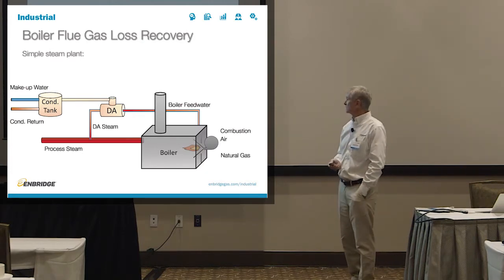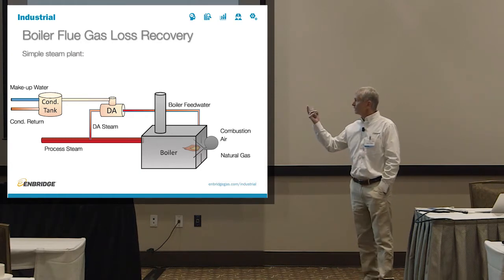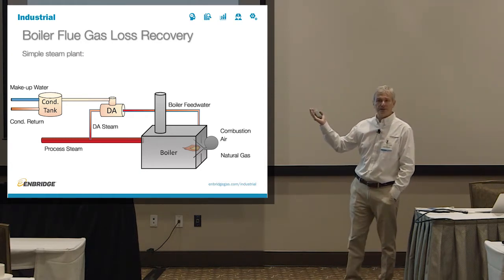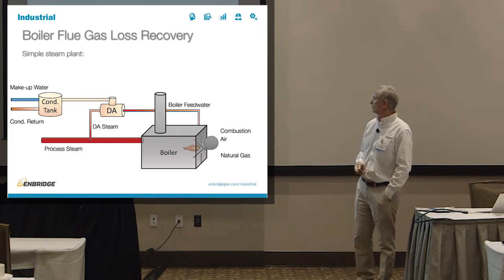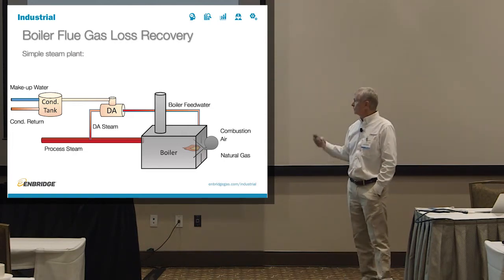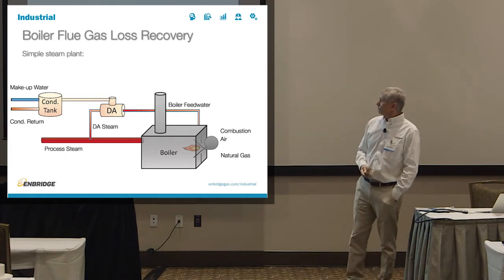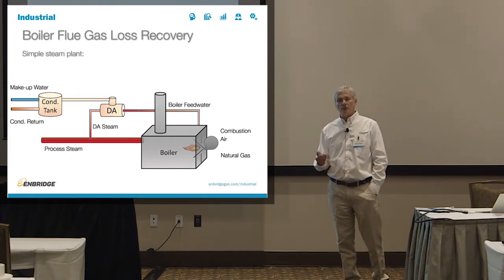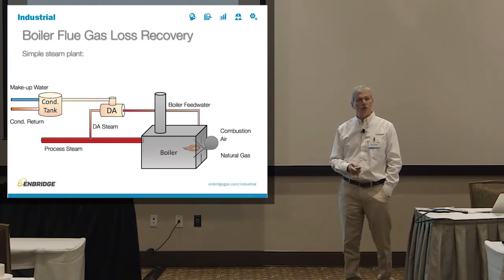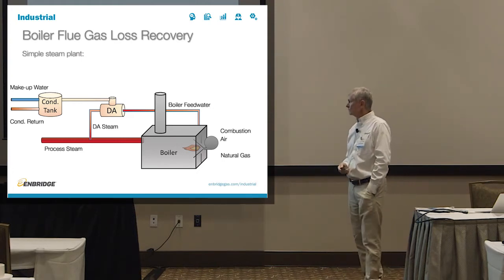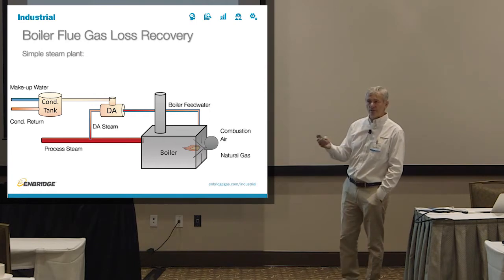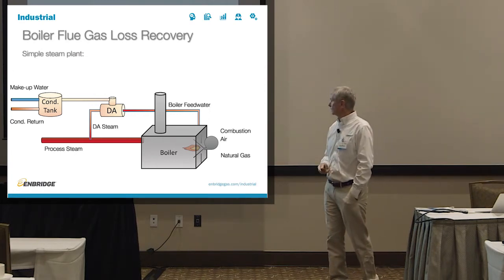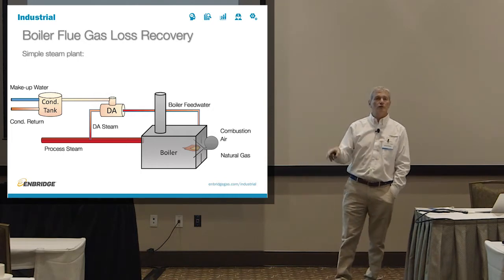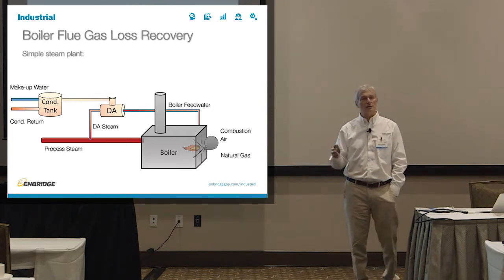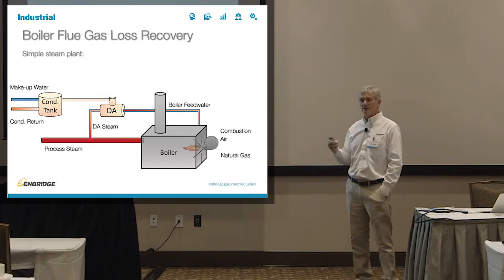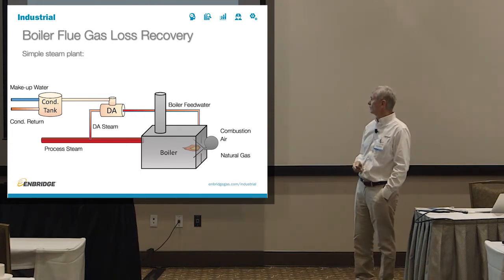So let's see how that looks in a simple steam plant. You usually have a boiler, you have the deaerator, and sometimes you have a condensate tank to return some of the condensate back. You put in natural gas, and combustion generates heat, which generates the process steam, and part of that steam goes into the deaerator because you have to get rid of the oxygen in the stream. Makeup water and the condensate return, some mixture thereof, goes into the condensate tank. Then the water from the DA goes into the boiler as boiler feed water, because now it's purified. That's a typical steam plant system, very simple.